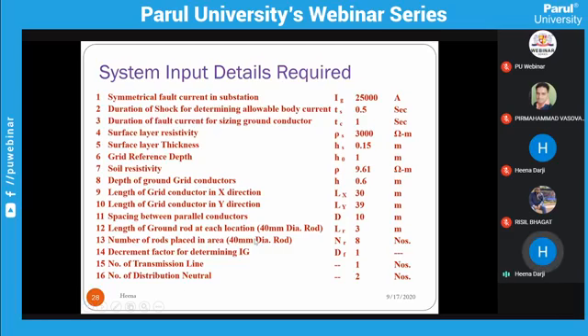Now, length of ground rod at each location. We have learned that your ground rod is buried in the ground not less than 3 meter. This is 40 mm dia because the earth resistivity is high. Now, number of rods: how many rods are used for this substation is NR, means numbers. Now, decrement factor for determining IG, that is 1. Now, how many incoming and outgoing lines: the transmission line is 1 and the distribution side is 2.